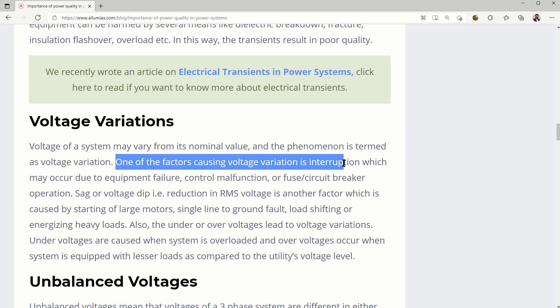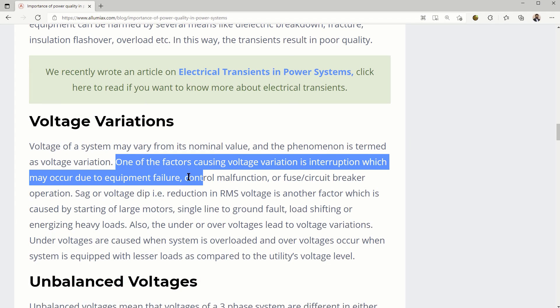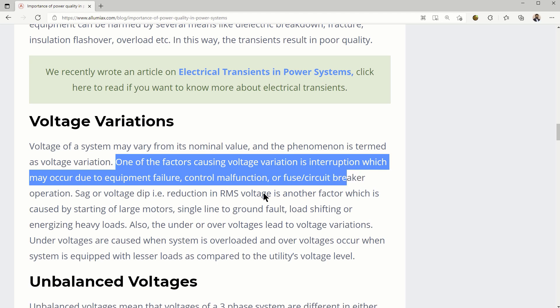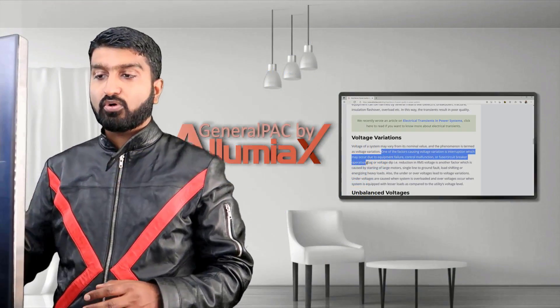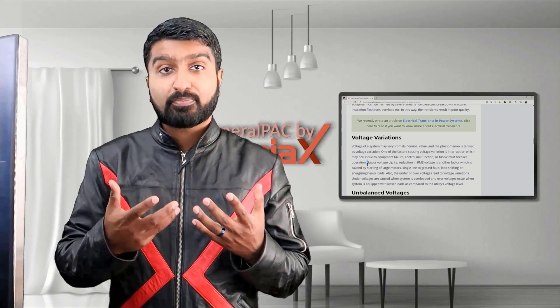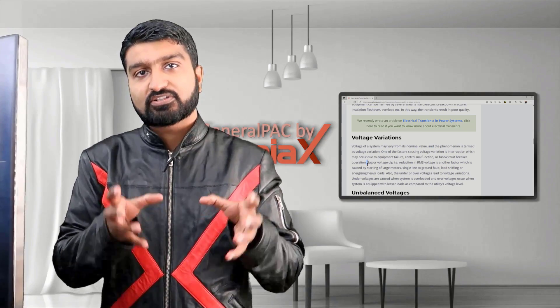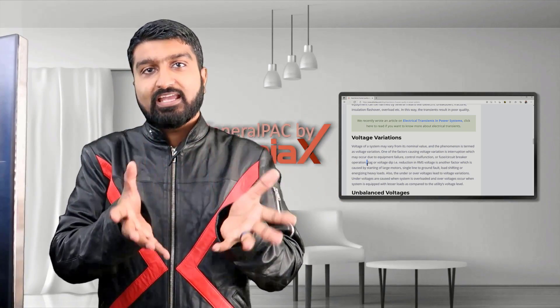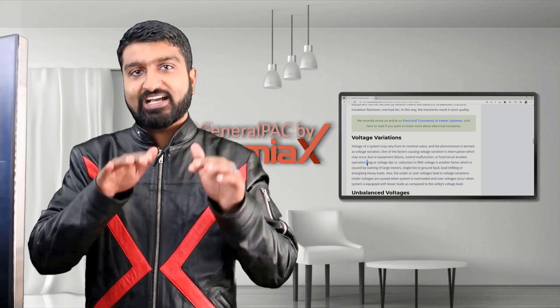One of the factors that cause voltage variation is interruption, which may be caused by equipment failure, control malfunction, or fuse or circuit breaker operation. I've dealt with systems where if a fault occurred and a circuit breaker operated and opened to interrupt that fault so it could be isolated, that caused a system impact and the voltage actually fluctuated as a result of that.